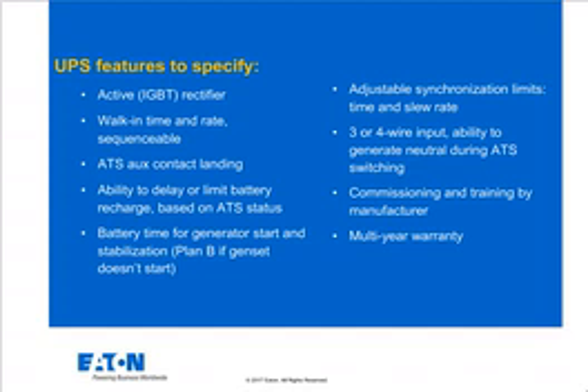Now, the same idea for the UPS. What kind of UPS features are important to make sure that the UPS and the generator work happily together? Well, the first one is this thing we've been talking about that we call an active or an IGBT rectifier. And IGBT simply means the type of transistor that's used in the rectifier, which acts as an active harmonic filter.